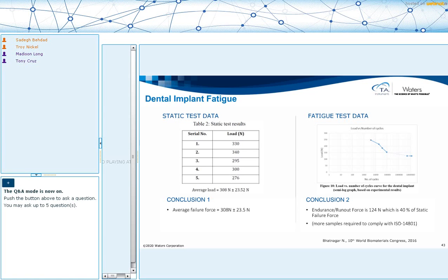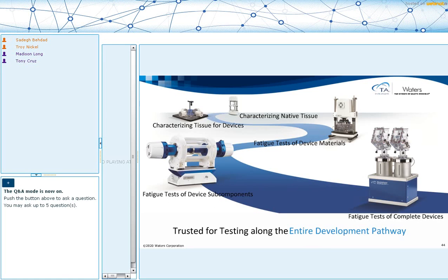And usually, they found out that 40% of the maximum static failure force is where you can get your endurance limit and sort of infinite fatigue life. And that's consistent with other literature values. A lot of times, at least for pure materials, you'll see that your endurance limit is somewhere between 30 to 40 to 50% of your maximum static strength, and this is right in the middle of that.